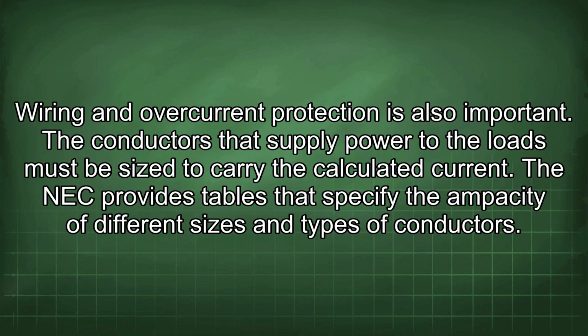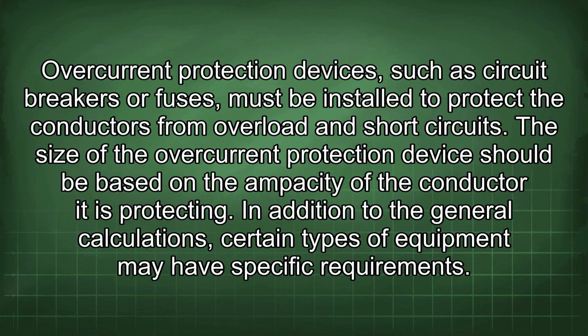Wiring and overcurrent protection is also important. The conductors that supply power to the loads must be sized to carry the calculated current. The NEC provides tables that specify the ampacity of different sizes and types of conductors. Overcurrent protection devices, such as circuit breakers or fuses, must be installed to protect the conductors from overload and short circuits. The size of the overcurrent protection device should be based on the ampacity of the conductor it is protecting.